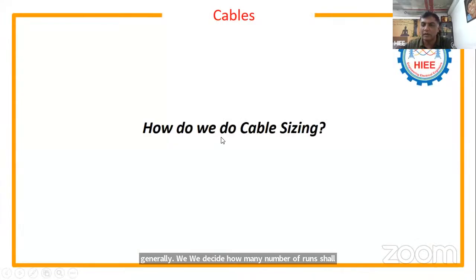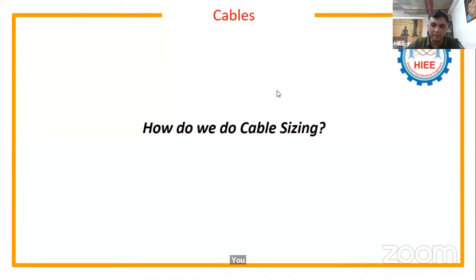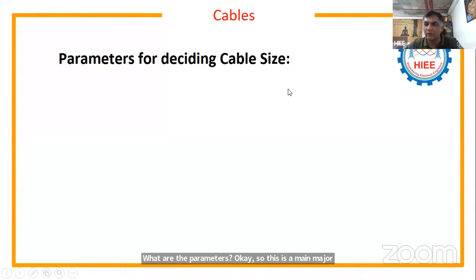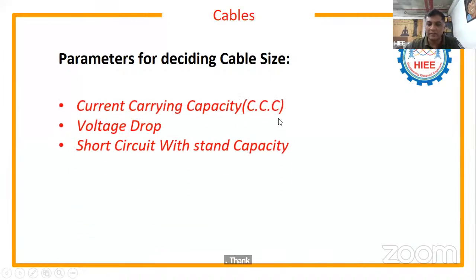Okay, so once you understand the cable, now we need to know how to do the cable sizing calculation, or what are the parameters that decide the cable size. Okay, so this is a major important thing which we are looking for. The first and foremost point is the current carrying capacity of the cable. Cable sizing is nothing but conductor sizing.